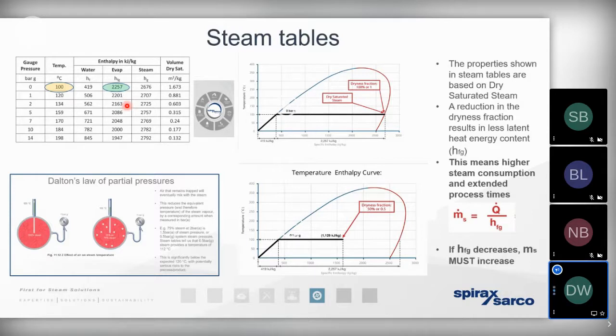So just to clarify what we've gone through in previous weeks, if we're distributing steam at a nice high pressure, let's say 10 bar gauge, then the temperature of the steam at 10 bar gauge is going to be 184 degrees. In other words, the condensate that exists in that distribution pipework will also exist at the same temperature, 184 degrees. It can exist as a liquid because of that pressure.